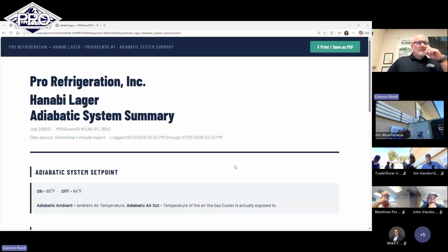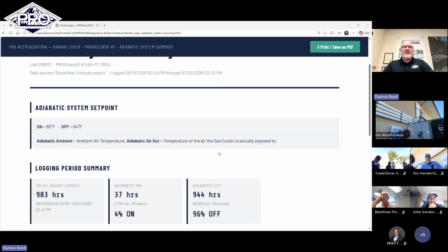Okay, awesome. So the adiabatic system, I wanted to talk about the set point. We engage the adiabatic right now if the ambient air temperature is 85 degrees or above. So if it's 85 degrees out, we should expect to see the adiabatic running, and then it stays on unless the ambient temperature drops to 84 degrees. So that's what we're looking at.